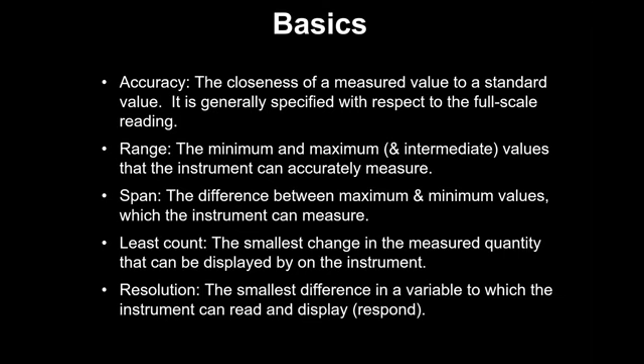But when we select an instrument, we have to see what the accuracy of the instrument is with respect to the reading we are taking. We need not go purely by saying that this instrument has 0.5% or 0.25% accuracy. But for the reading you are going to take, how accurate your values are likely to be, that needs to be analyzed. And as a part of that, the rest of the things will come.